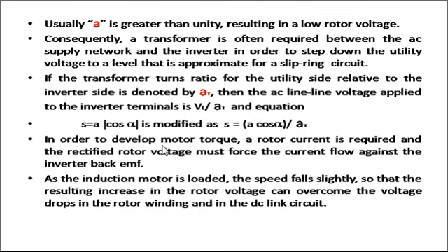Now, in order to develop motor torque, a rotor current is required, and the rectified rotor voltage must force the current to flow against the inverter back EMF. As the induction motor is loaded, the speed falls slightly so that the resulting increase in the rotor voltage can overcome the voltage drops in the rotor winding and in the DC link circuit. There are voltage drops in the rotor winding as well as in the DC link circuit.